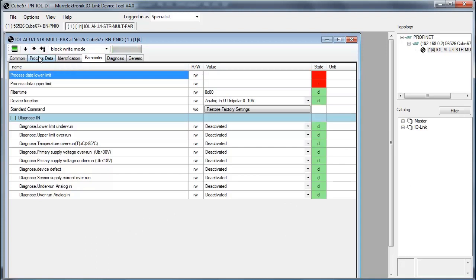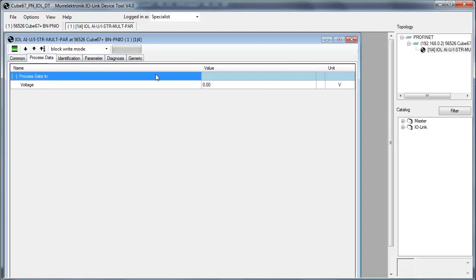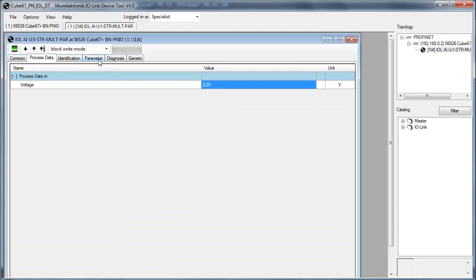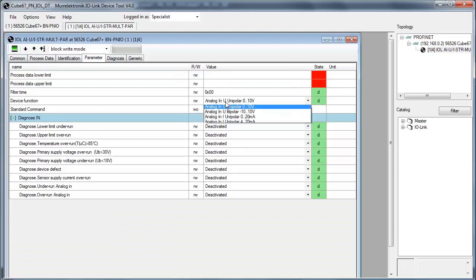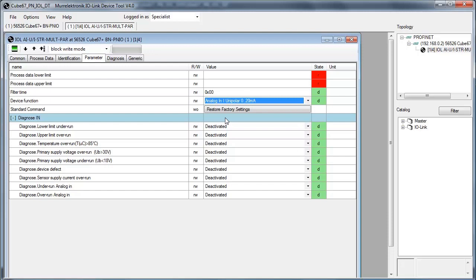Go to Process Data tab. The current value is voltage. To change this value, go to the parameter tab. Open the drop-down menu device function and choose 0 to 20 mA.